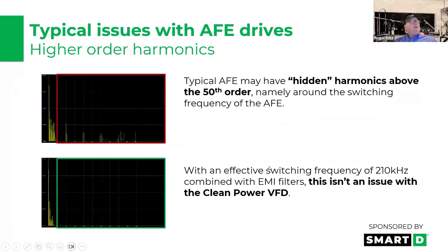And this is an idea of what you see on a scope Fluke meter. That shows the standard VFD, where you see all of these harmonics going all the way out, clear to the 50th order, meaning like 5,000 hertz noise. So what we're really doing is creating a radio. And you can actually hear the switching in the motors. You can hear it on the power lines. If you've got an AM radio, it radiates off. So all this additional multi-harmonic current also draws additional power.